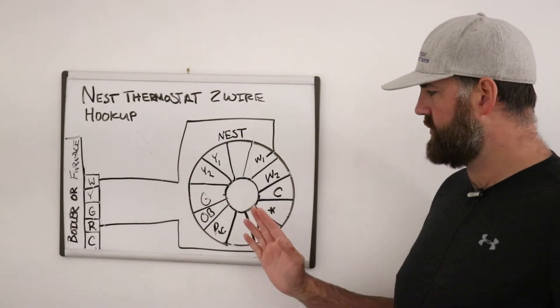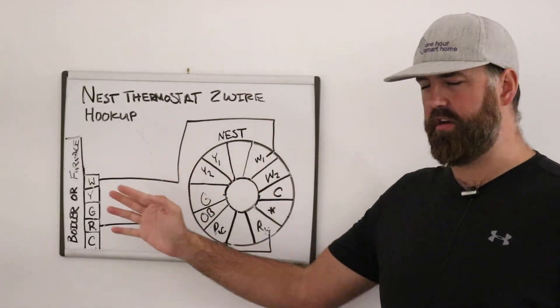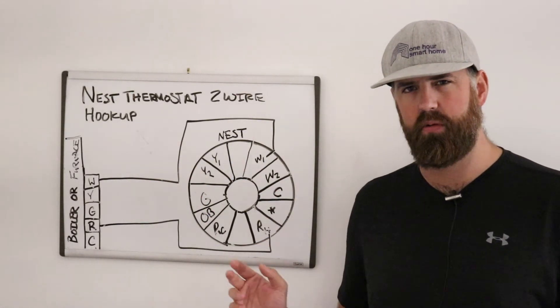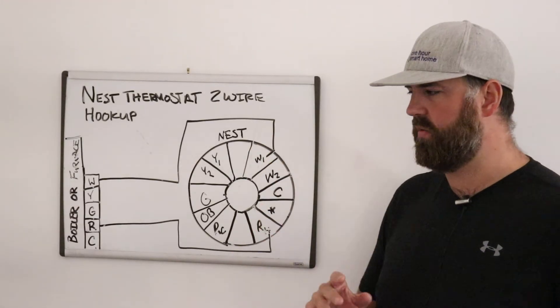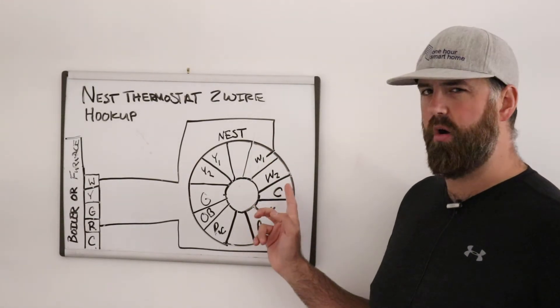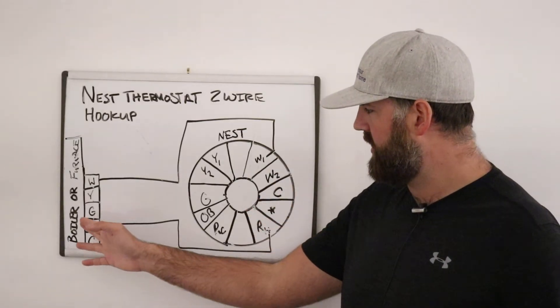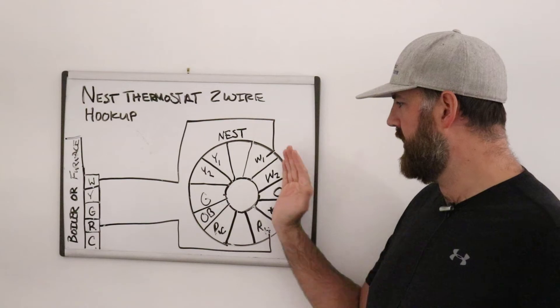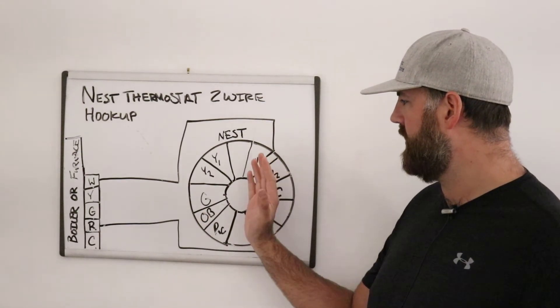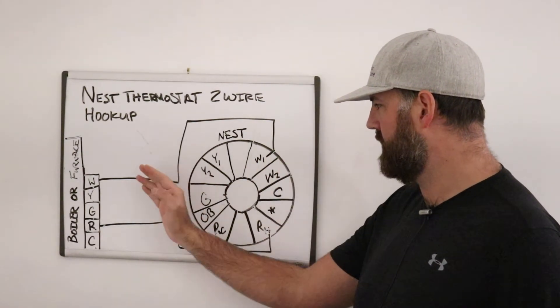So how the nest works is it will charge with R and W. And for most people, I think it's like 90% of people, you'll never have any issues with power or anything like that. You don't need to worry about it. But in a small number of cases, the boiler or furnace does not put enough power out that the nest can suck the power off of it while completing the R to W circuit.